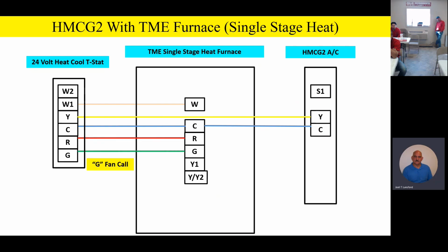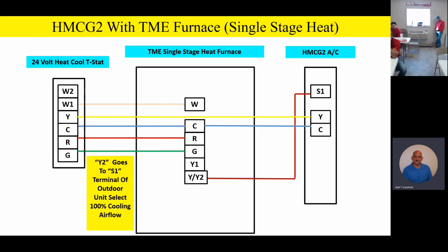G is fan. Now you're going to notice something, because it's a furnace, we've actually got hard terminals on there, say Y1 and Y2, right? So Y2 is going to go up to S1. Y2 will go to S1 because that's our high-speed airflow commanded by S1. And your Y1 terminal will go right up to the yellow wire going to the outdoor unit. So basically, when the thermostat calls for cooling, it's going to call for 60% airflow, Y1 on the unit.